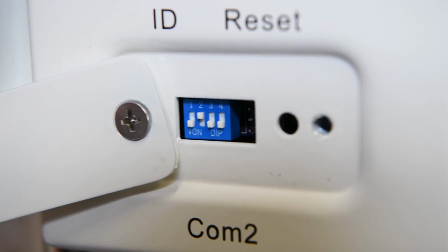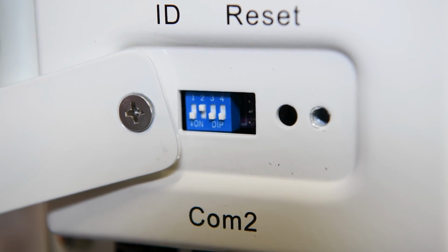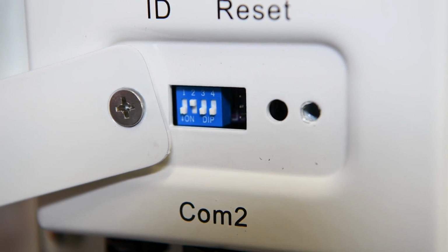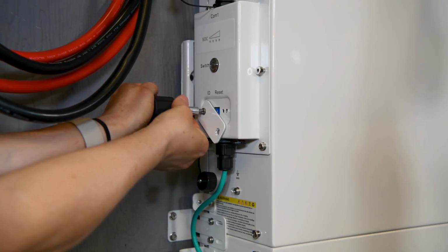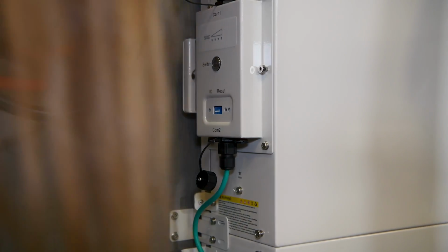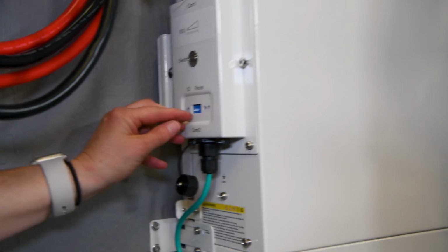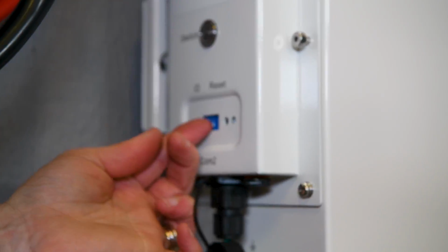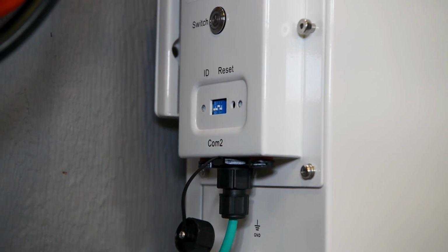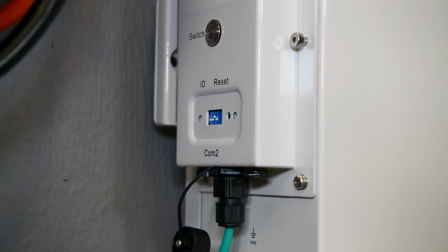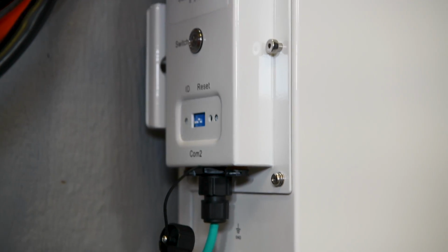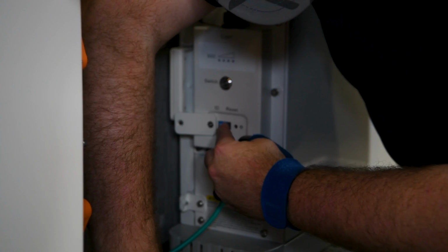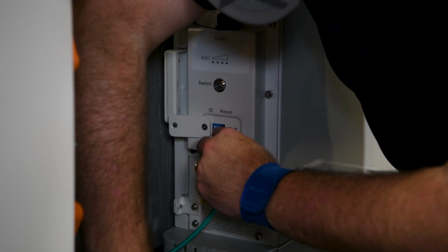Next up, it's crucial to assign the correct ID addresses to each battery module. You'll find the ID descriptions detailed in the manual on page 16, and it's important to pay close attention to these. While the functional order from top to bottom isn't critical as long as each battery has a unique ID, for troubleshooting purposes, it's wise to organize them in a manner that makes sense. BigBattery suggests labeling each stack in descending order, beginning with the controller box at the top. This methodical approach facilitates easier identification and management of your battery modules.